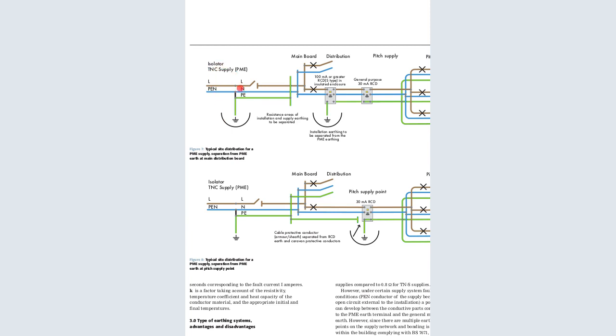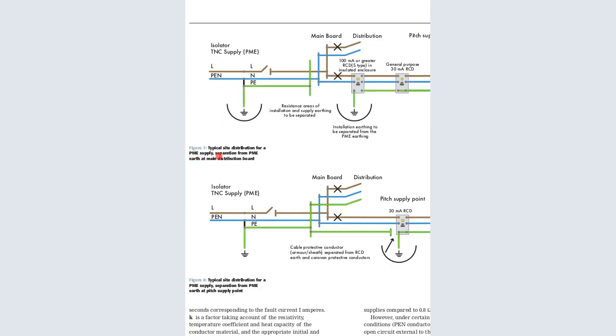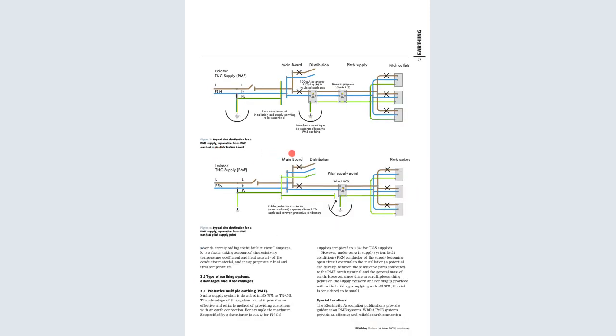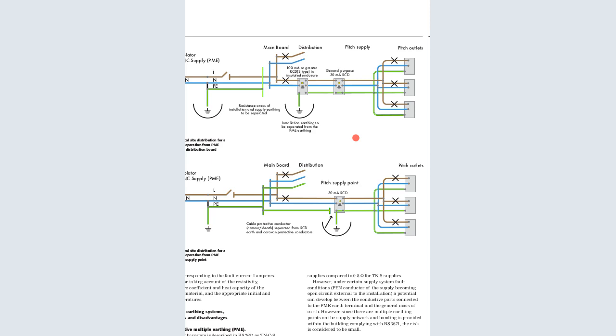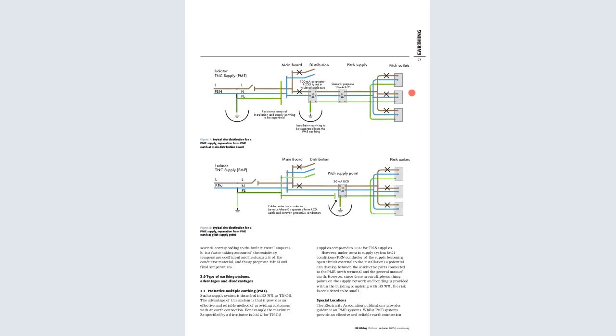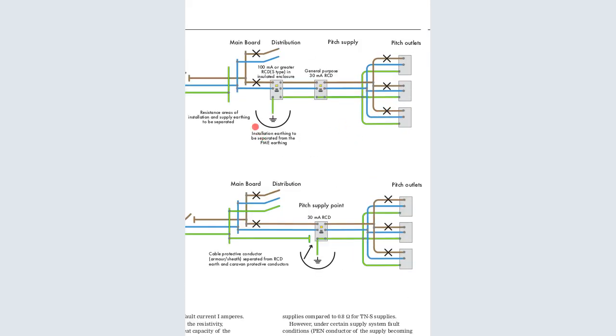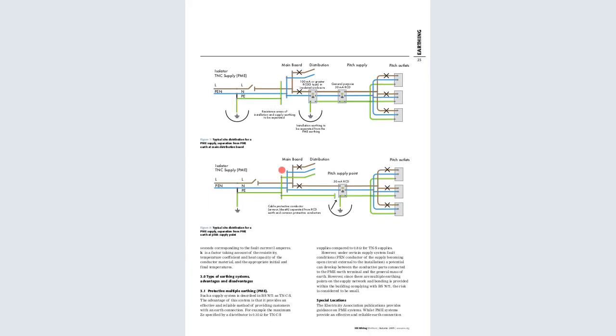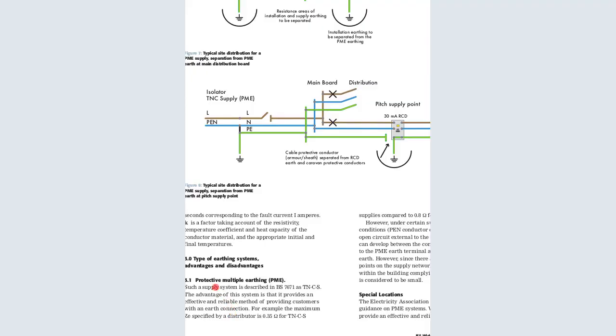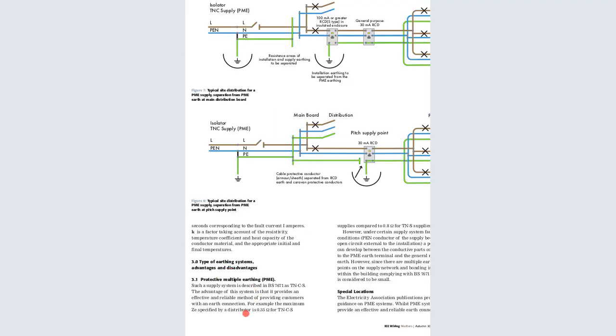This is the typical site distribution of the PME supply, the PME earth at the main distribution board. This is how the PMEs are distributed. This is normally done by the supply company, which is Kenya Power. You can now see the TN-C-S and the typical separation, the types of earthing system, advantages and disadvantages.